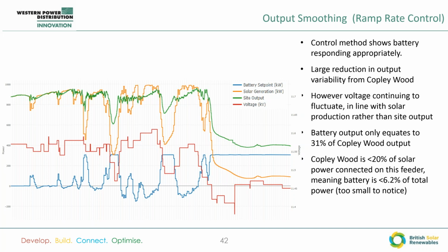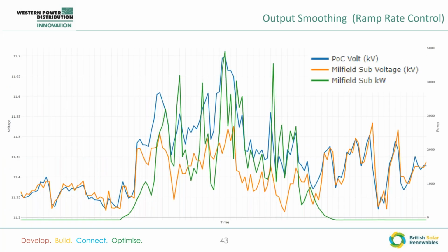But we're still getting grid voltage fluctuation, even though we're reducing these dips by 50% at least. Why? Well, it's High Hill again. Although we're 31% of this park's rating, we only work out to being 6.2% of the overall power flowing from the site. So it's too small to have an impact. But again, we have proved that the battery can fulfill this use case and is working reliably.